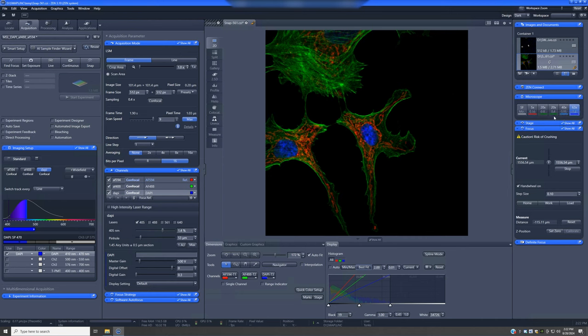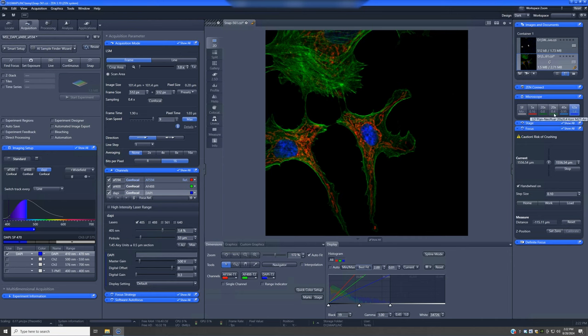The 20x0.4 is a specialized objective that is compatible with plastic multi-well plates. If you use plastic multi-well plates, you should use this objective and only this objective aside from the 5x, which I'll discuss in a moment. It also is compatible with something called PlasDIC, which is a form of contrast enhancement that is compatible with plastic and gives results similar to DIC. So if you're trying to image things through plastic plates, this is a good option.